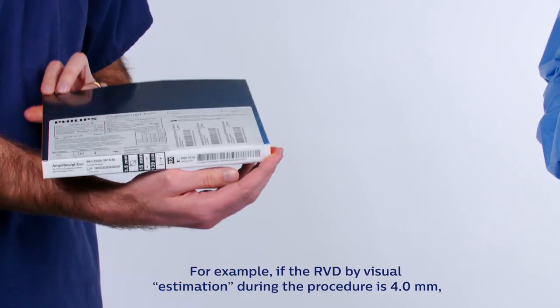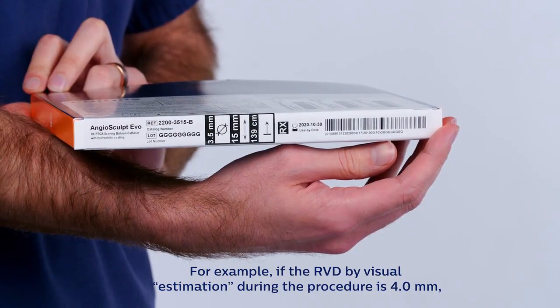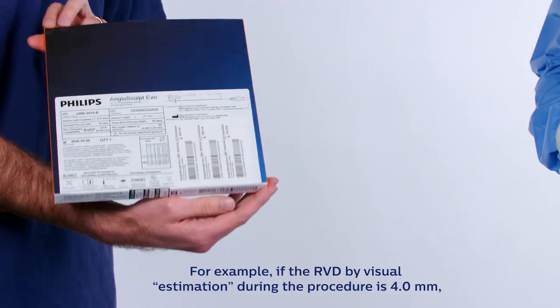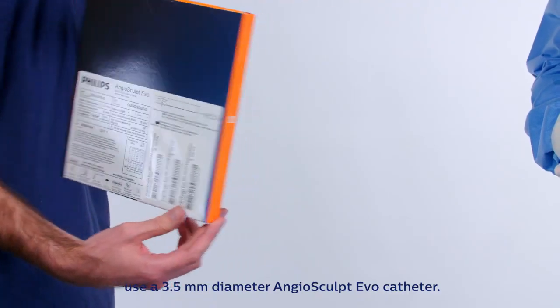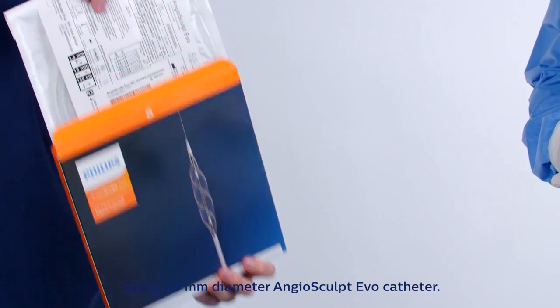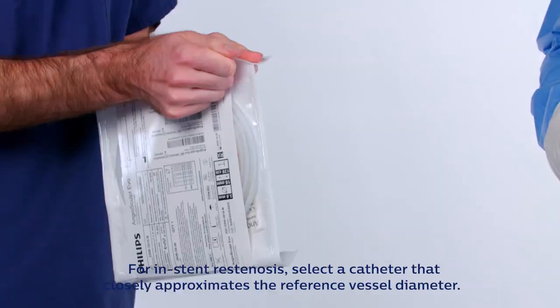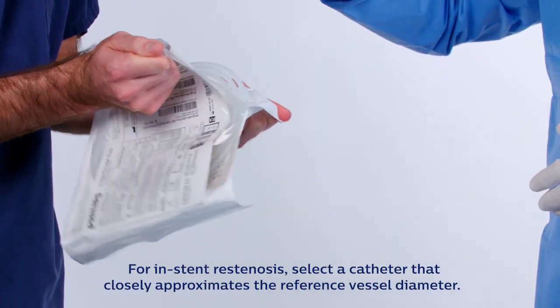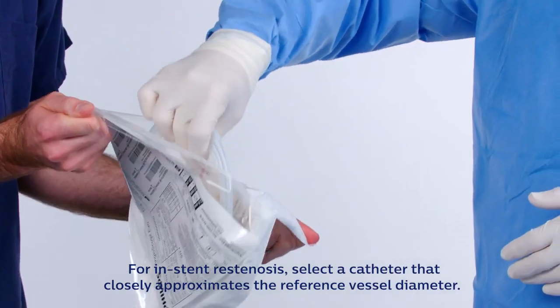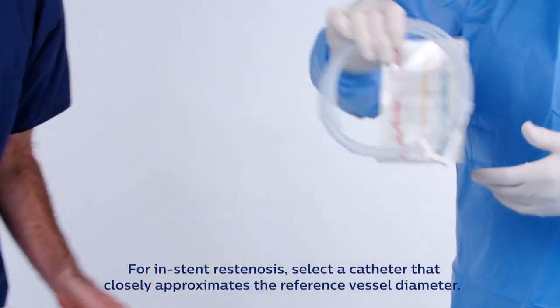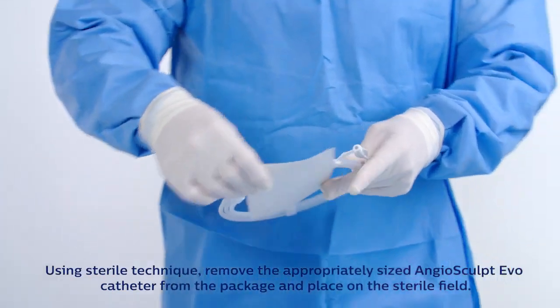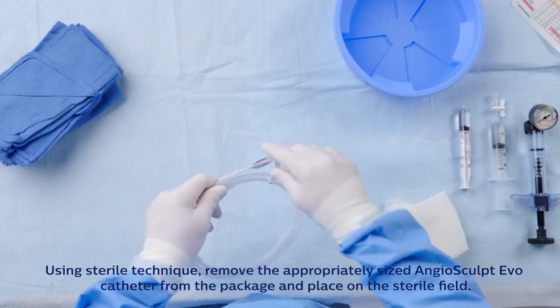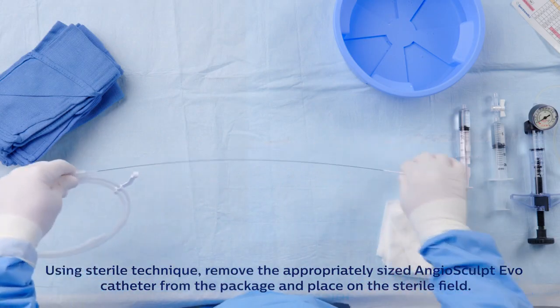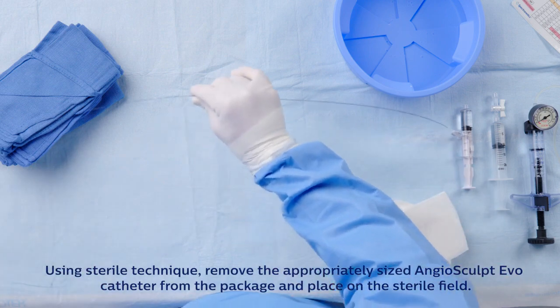diameter. For example, if the RVD by visual estimation during the procedure is 4 mm, use a 3.5 mm diameter AngiosculptEvo catheter. For in-stent restenosis, select a catheter that closely approximates the reference vessel diameter. Using sterile technique, remove the appropriately sized AngiosculptEvo catheter from the package and place on the sterile field.